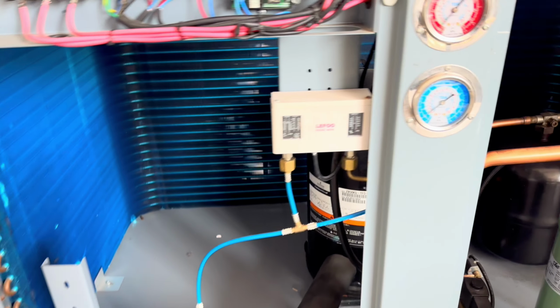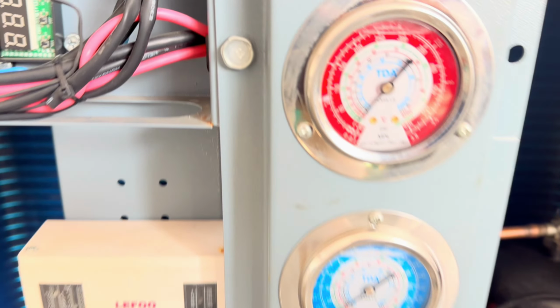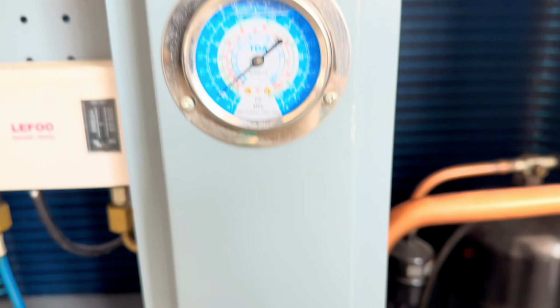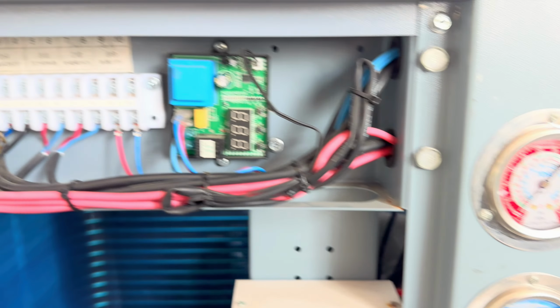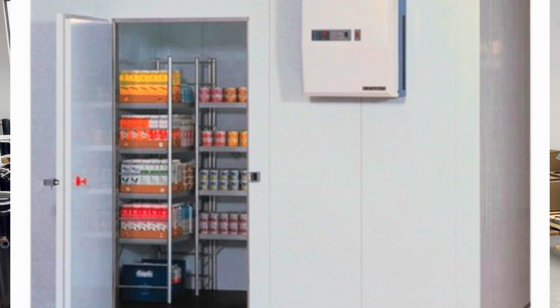The disadvantage of this compressor is that if it breaks down, it's not easy to fix. Sometimes it's not worth fixing it; it's better to just replace it with a new compressor. Another disadvantage is that it's not suitable for very large cooling capacity or big cold rooms. It can go from 1 horsepower up to 10 horsepower. I recommend it for the most common applications, like small walk-in chillers, walk-in freezers, and display cases in supermarkets.